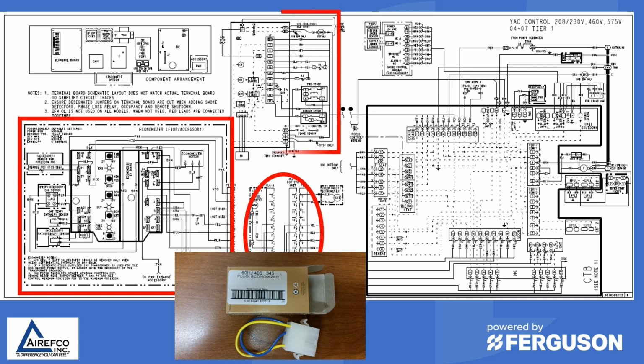You can also isolate the gas heat board from the system in case there is a short or a problem in the gas heat section. On the main board, you have fire controls, fire dampers and fire alarms, which can also keep the system from operating. The main board is simply a connection point.